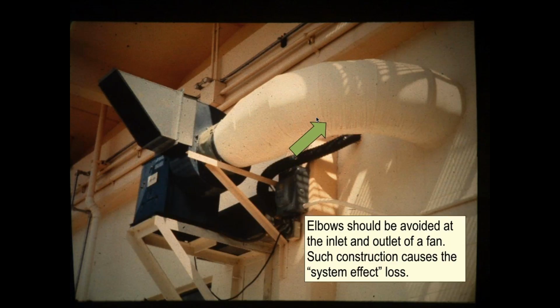diameters from the fan. So if this is a 12-inch duct, you don't want an elbow before 6 feet, closer than 6 feet to that fan. If it's a 24-inch duct, you don't want an elbow within 12 feet of that inlet. Same on the discharge, except on the discharge you can tolerate a little bit more. It's 3 times the diameter. This is all written down for us. We're going to get to this.